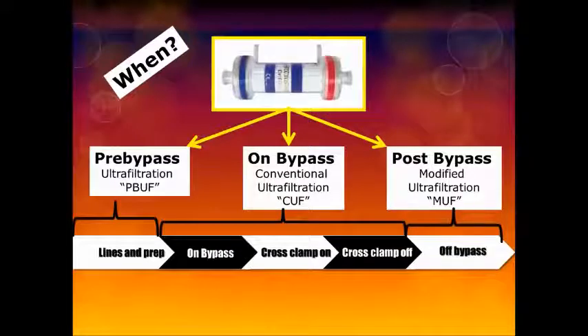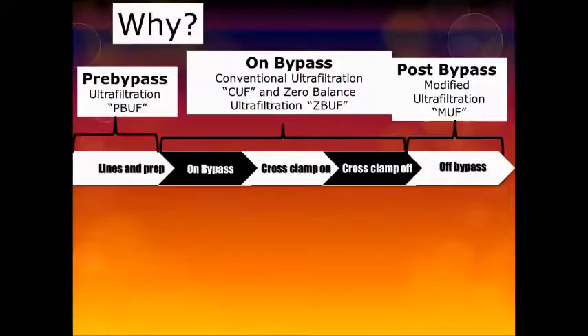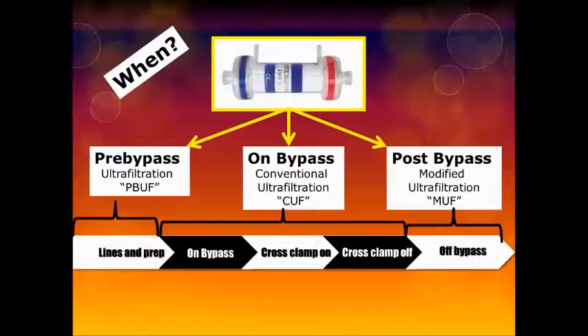And that universal use is because the hemoconcentrator can be used during all of the distinct phases of cardiopulmonary bypass. Before bypass with pre-bypass ultrafiltration, while on bypass with conventional ultrafiltration, and of course, after bypass with modified ultrafiltration.